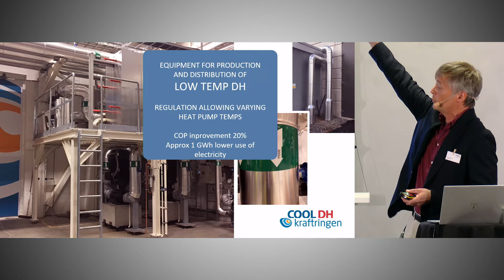So why low temperatures? Well, several reasons. One I already talked about: heat recovery is more efficient. As I said, we are expecting and seeing very energy efficient buildings being erected, and it's important to keep the heat losses down, because otherwise it won't be energy efficient. Keeping the heat losses down is easier if you keep the temperatures lower. That goes both for the distribution system and also for the systems inside the building. Temperature losses drop if you can lower the temperature.